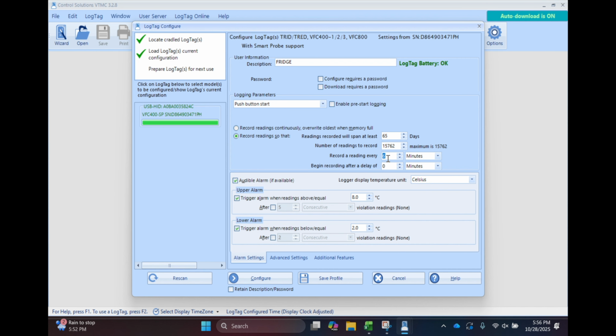It's telling me that if I read every 5 minutes, using all the available memory to the logger, I have logs internally stored on the memory of the logger for up to 45 days. That just means you must download your logger before the 45th day of logging, otherwise it will stop.